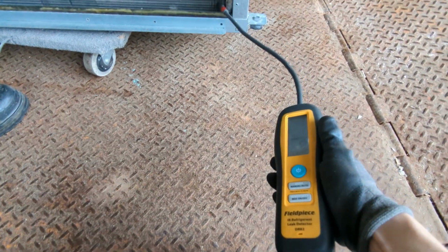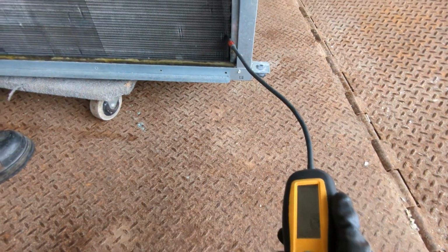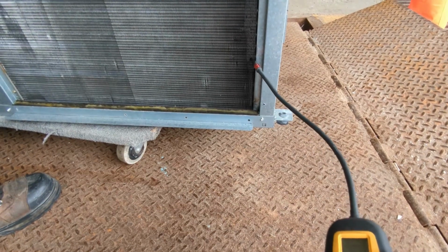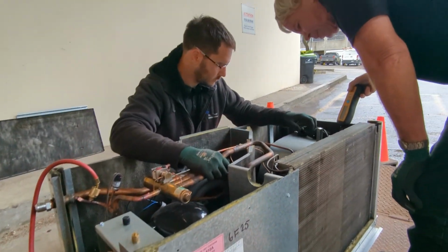Our digital leak detector, our sniffer, didn't pick up anything at all. We bumped up the pressure to about 300 psi, still nothing. Sometimes you can hear it, sometimes it'll be a little hiss, but nothing like that at all. Still nothing on the digital leak detector. And then my dad had the great idea of using a heat gun to heat up the evaporator coil to see if that would expand the pipes or give any kind of indication of a leak. And our leak detector went nuts when that smoke came out.